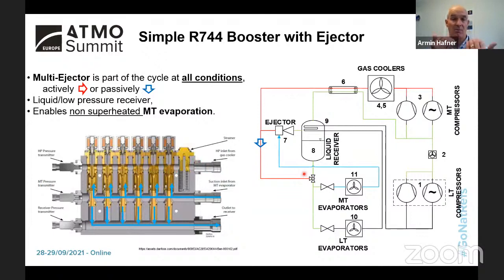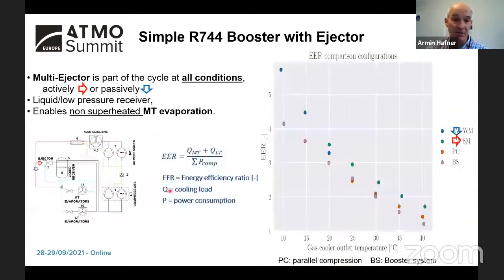It's distributed at the lower pressure level to all the small expansion devices in front of every evaporator. By doing so, we still maintain the flow back to the ejector, but now the flow goes through the ejector passively and just back into the receiver. We have measured these pressure drops in the system. I will show you in a minute. So that means we have a very simple system, just switching between ejector mode, passive and active mode, and nothing else. And by doing this, we can have a high efficiency on the evaporators and a simplified system.